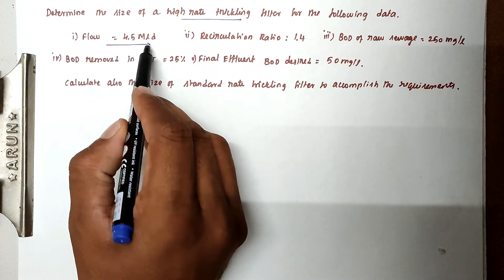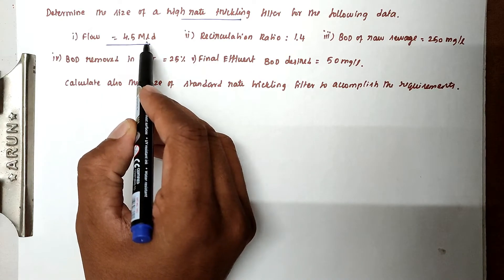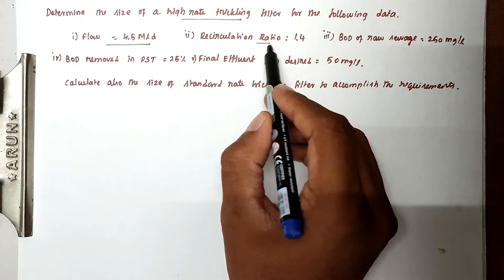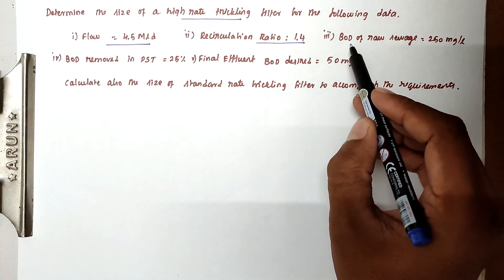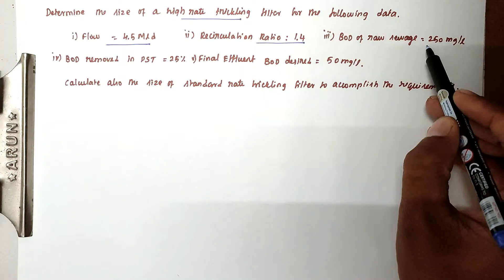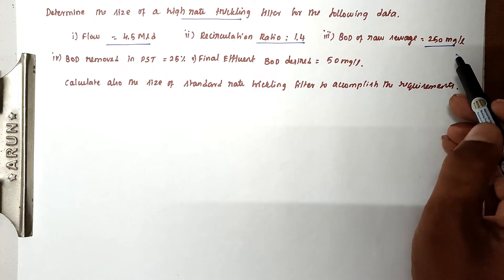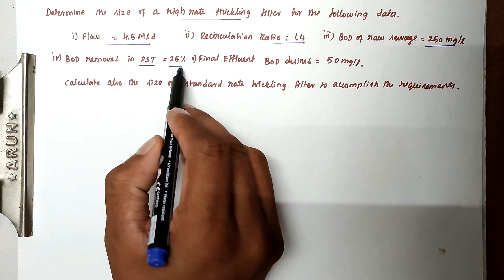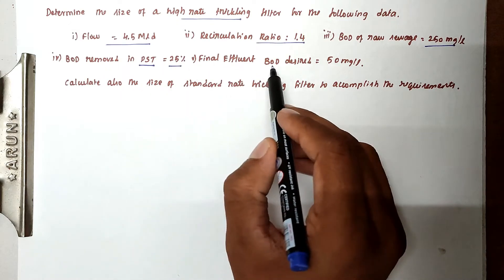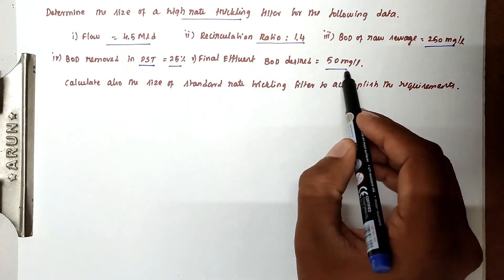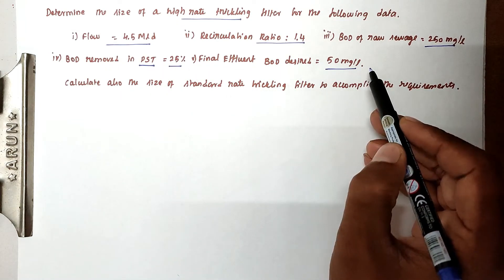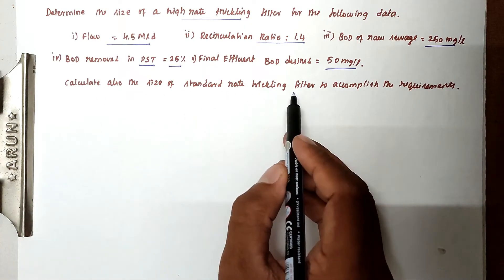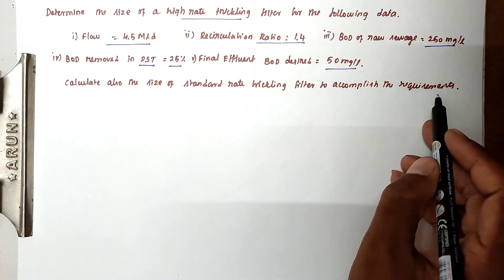The given data: flow is 4.5 million liters per day, recirculation rate is 1.4, BOD of raw sewage is 250 milligram per liter, BOD removal in primary settling tank is 25%, and final effluent BOD desired is 50 milligram per liter. Calculate the size of standard rate filter to accomplish the requirement.